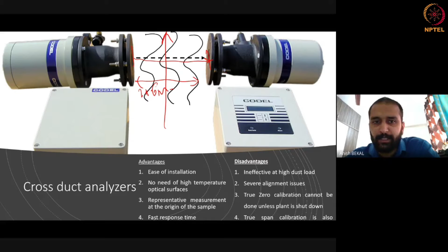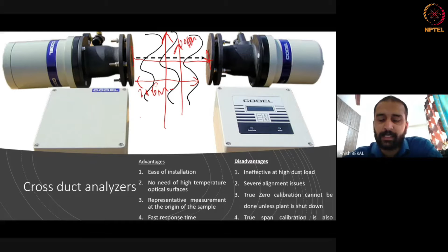Okay, when you have these kind of systems, in some cases a true zero is not possible, because if you want to take a zero here, you have to wait for the plant to shut down, or even the span calibration. So span calibration, what I mean is, I basically want to put a fixed concentration, for example 100 ppm of the gas in this path, and see what the instrument is measuring. That's one way of telling whether the instrument is working. So all those things are very difficult in these kind of schemes.